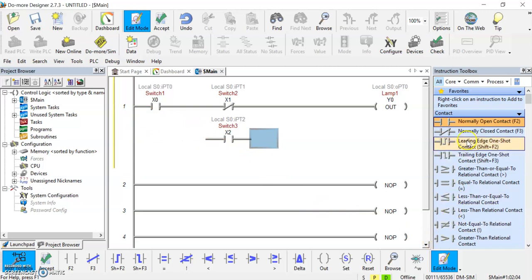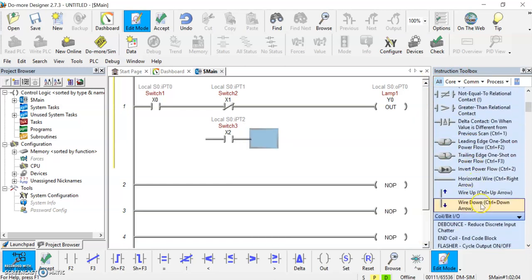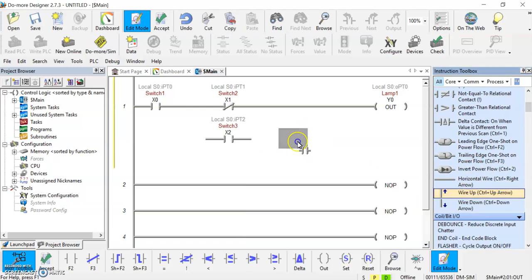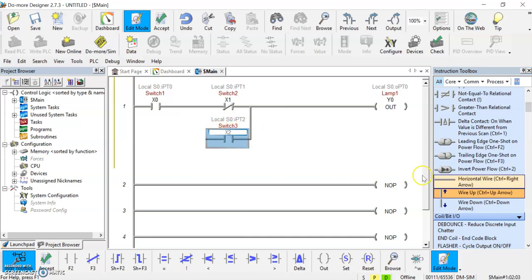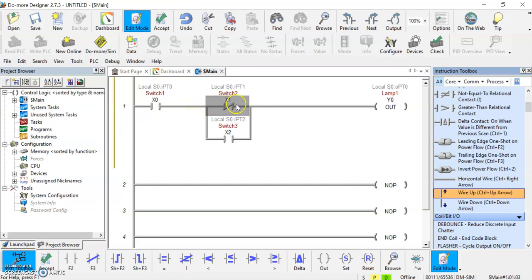We got to get that attached here. So if you go into your instruction toolbox on all and you scroll down here a bit, you're going to see a wire up. Let's just grab that and put that over there, and then we highlight this again so that it's blue here, and we'll do the exact same thing there. It will now have the instructions read through, and so when the PLC is scanning through here, it's going to go in both these directions and see what the state of both of these instructions are and see if it's going to affect our lamp 1.